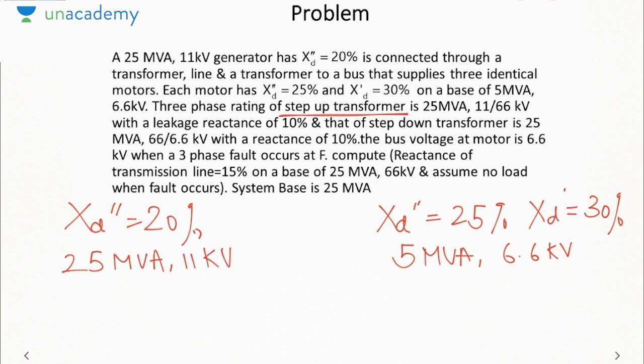The rating of the step-up transformer: the step-up transformer will be connected nearer to the generator because before transmission we will step up the voltage. It is 25 MVA, 11 by 66 kV, and the leakage reactance is 10%. Okay, step up is 0.1. Then the step down transformer is 25 MVA, 66 by 6.6 kV with a reactance of 10%. Step down is also 10%.